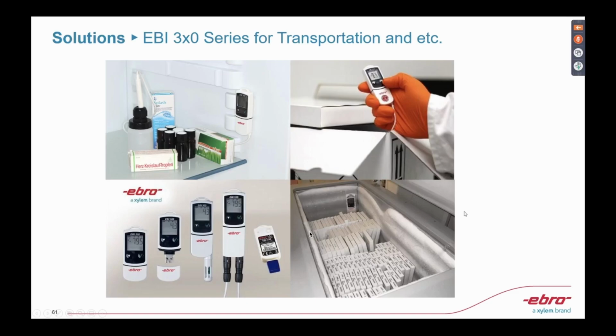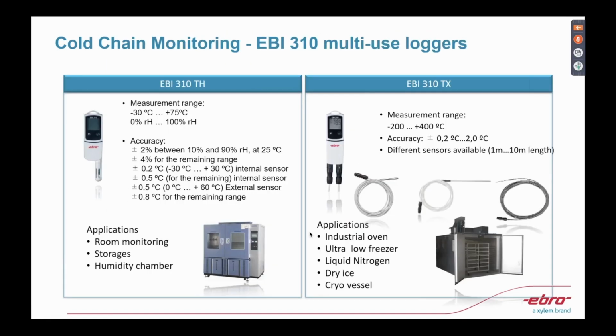It looks very simple, but this is actually one of the most interesting products I've seen at Ebro. Most of our pharma customers choose the EBI 310 because the accuracy is better, the sampling rate is smaller, and it has larger memory. But as I explained, these can be used in all different kinds of places. With the EBI 310 TX, you can even measure up to 400 degrees if you want. We have different sensors for you to choose from.